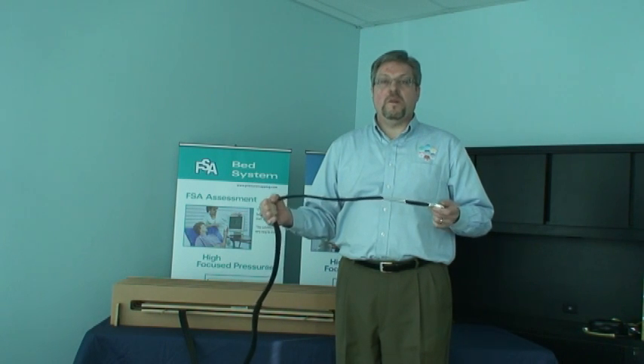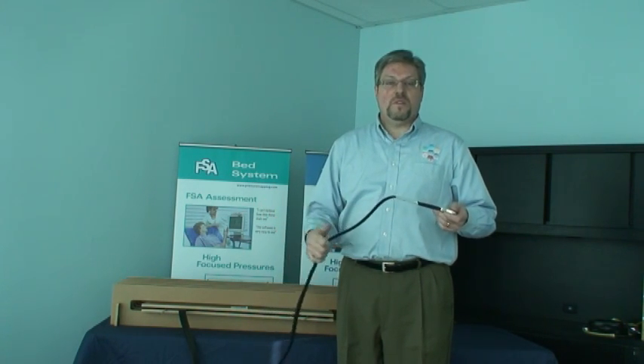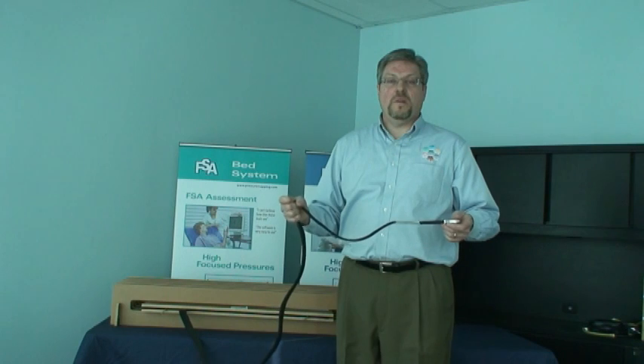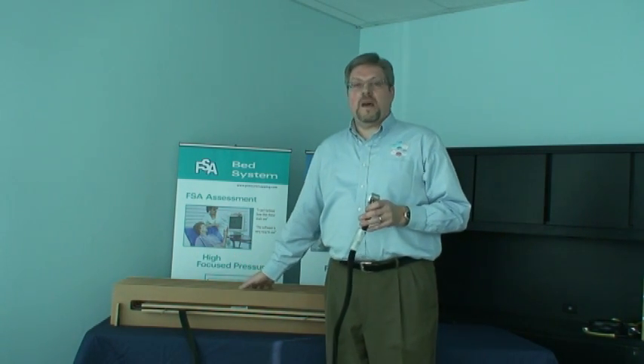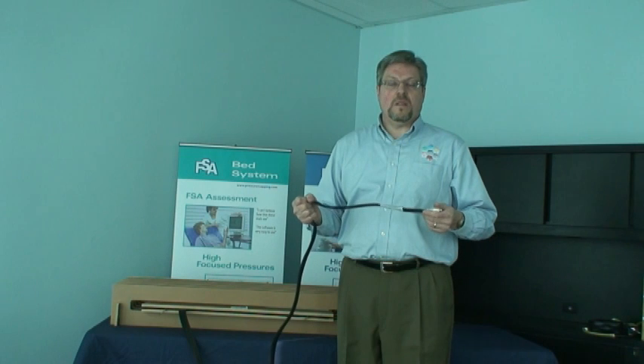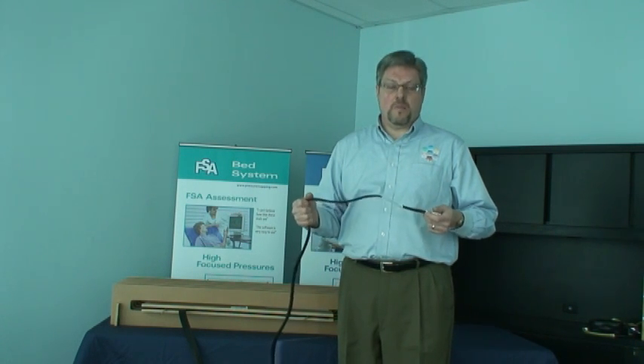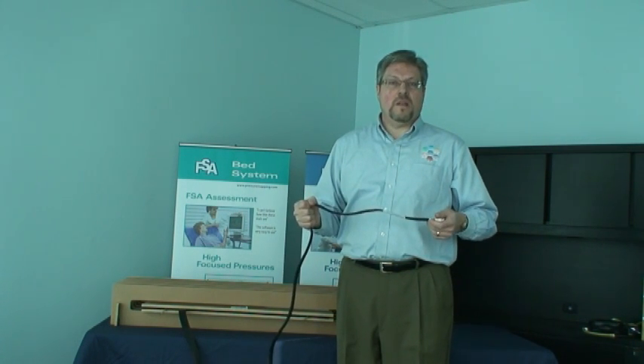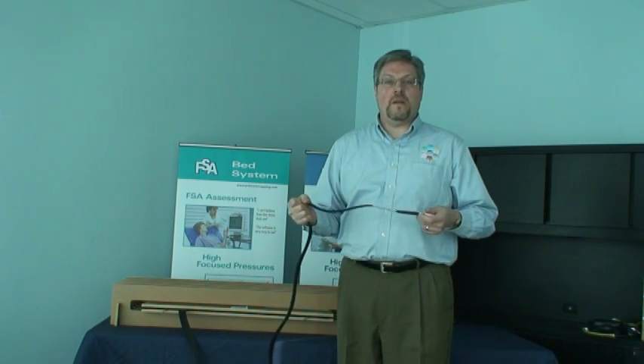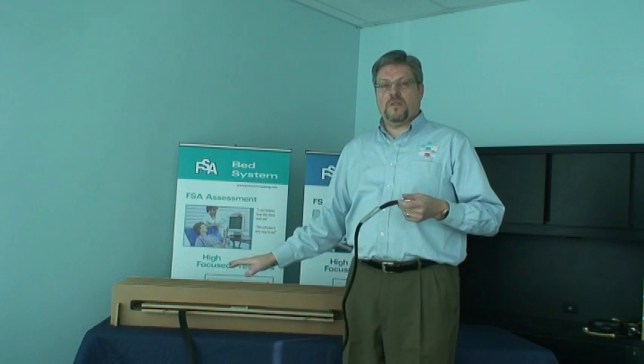If you're doing research, you may want to consider an auto-calibrator, which essentially is another black box that goes between the computer and the system, and it will do it automatically. So once you set it up and have an auto-calibrator attached, you would simply go to calibrations, tell the system you're using the calibration wizard, tell it that you're using an auto-calibrator, hit the enter key to start, and walk away. For a bed system, or for a seat mat like this, it would take about 20 minutes to do the calibration. For a bed, it takes about 40 minutes.